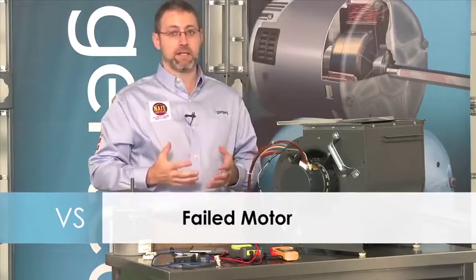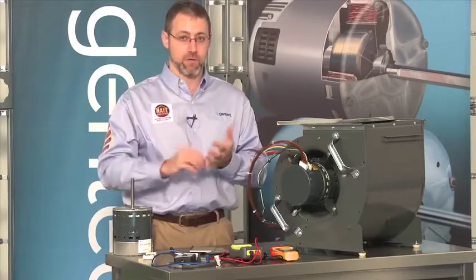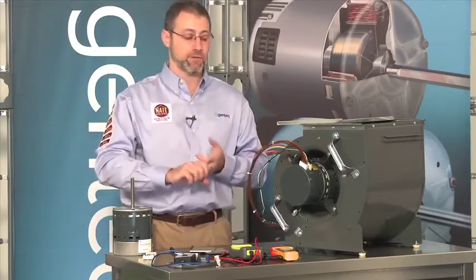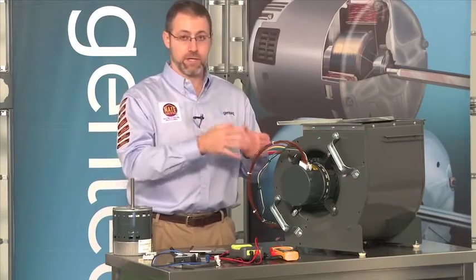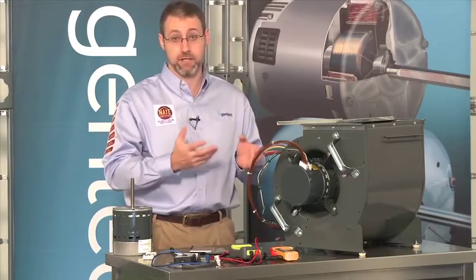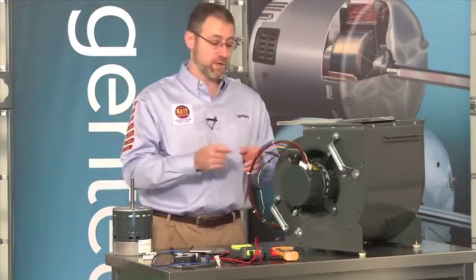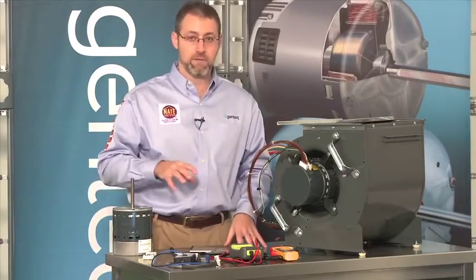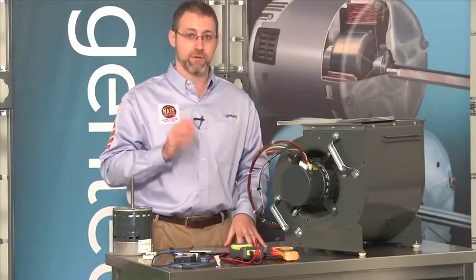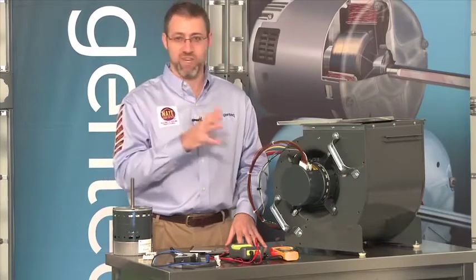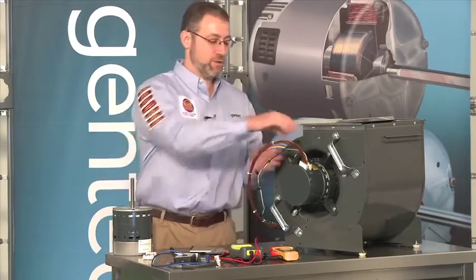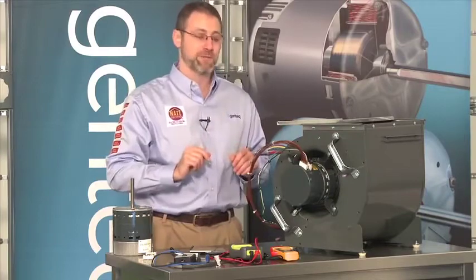So in my opinion, that's kind of a good thing. We're no longer troubleshooting run windings and start windings and capacitors. It's literally just, is the electronic device getting the 2 inputs that it needs to run? So let's start with the high voltage input. All of our variable speed motors since the first generation 1.0, which we haven't made for about 15 years, use a 5-pin connector. And I almost made a mistake there.